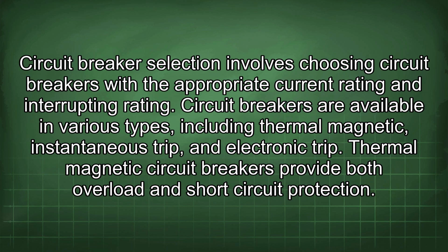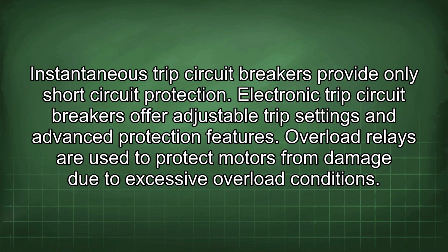Circuit breakers are available in various types, including thermal-magnetic, instantaneous trip, and electronic trip. Thermal-magnetic circuit breakers provide both overload and short-circuit protection. Instantaneous trip circuit breakers provide only short-circuit protection. Electronic trip circuit breakers offer adjustable trip settings and advanced protection features.